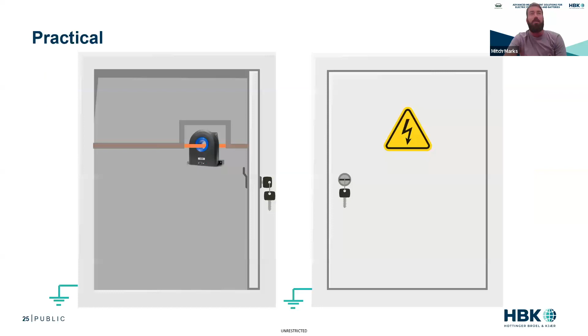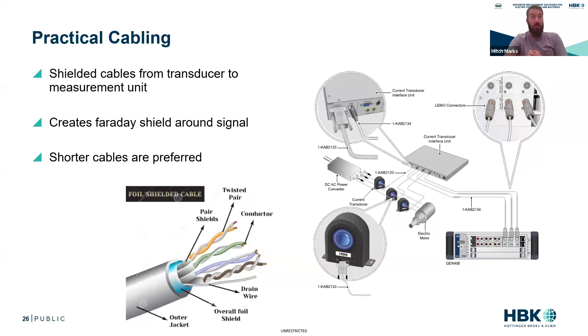As far as cabling, we want really nice shielded cables. Cables are expensive, but pay for the good cables. Having a closed shielding path from the current sensor to an amplifier to the measurement system is going to help us a lot. HBK offers a really nice path for that measurement, a really nice Faraday cage around it to prevent EMC and EMI issues. So use good cables, really look at your shielding and grounding path, and if possible, use a partner like HBK who can do a lot of this for you through the instrumentation.